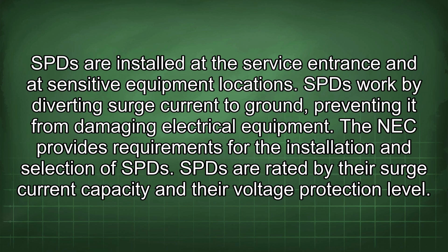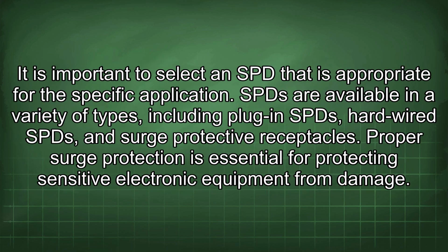The NEC provides requirements for the installation and selection of SPDs. SPDs are rated by their surge current capacity and their voltage protection level. It is important to select an SPD that is appropriate for the specific application. SPDs are available in a variety of types, including plug-in SPDs, hardwired SPDs, and surge protective receptacles. Proper surge protection is essential for protecting sensitive electronic equipment from damage.